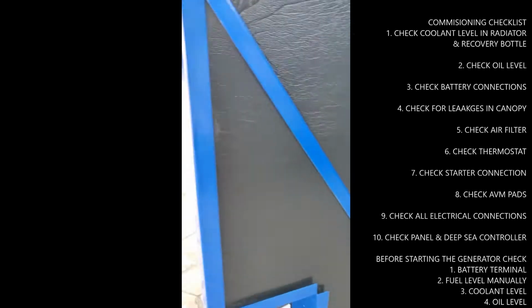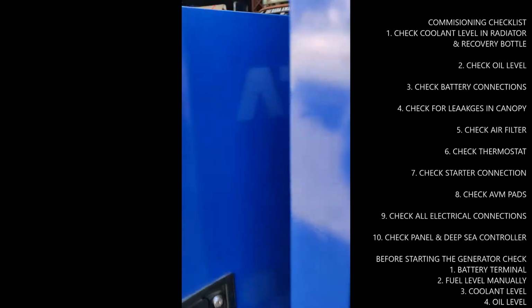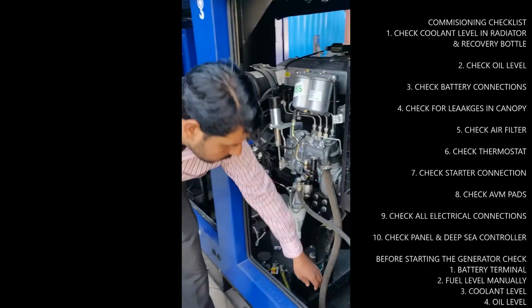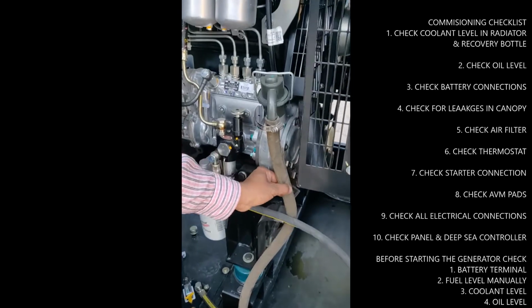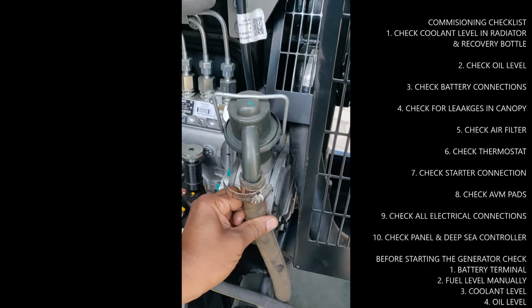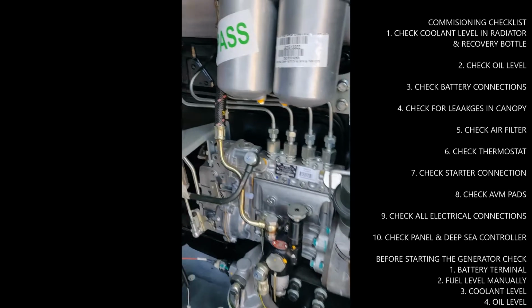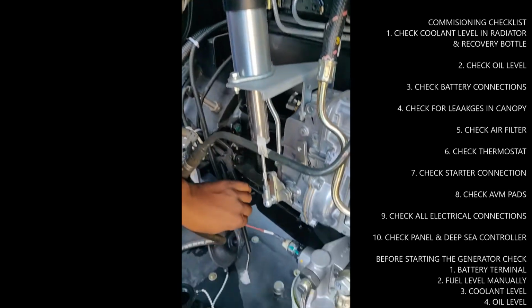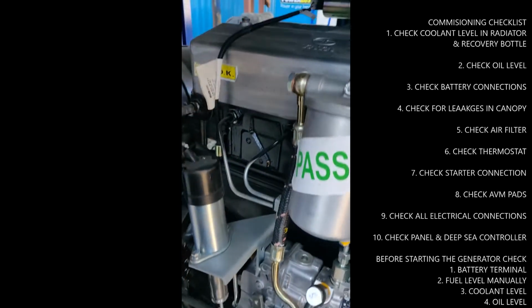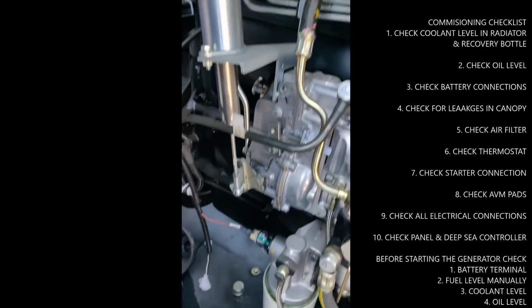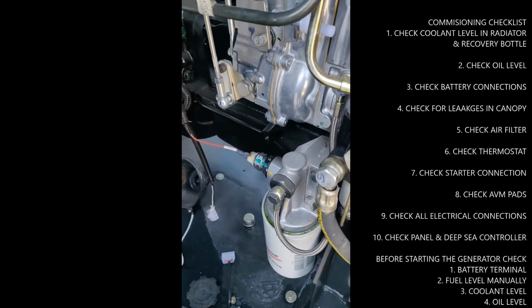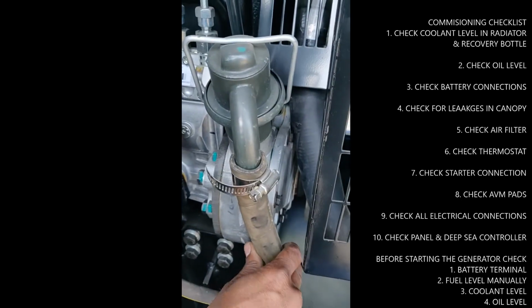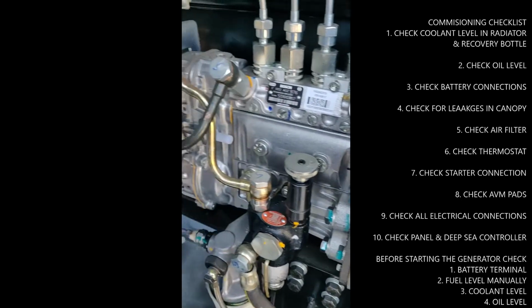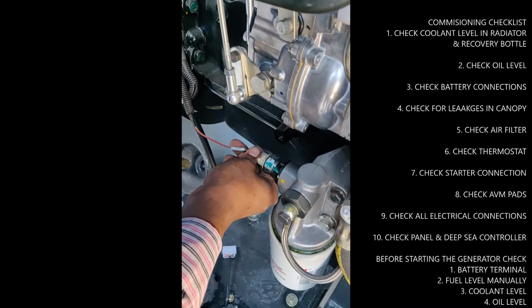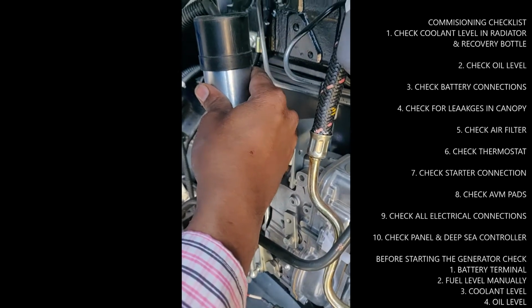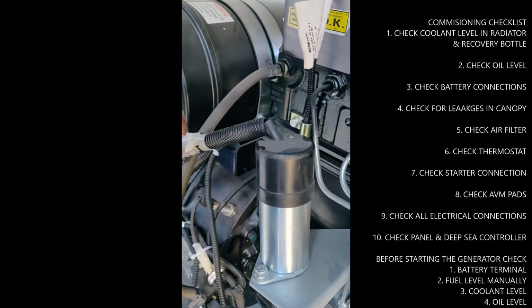Check the breather pipe that comes from outside the engine. This is the breather pipe. As you can see, it should be properly connected and fitted. Check the clamping of the pipe. Check that the solenoid coil and the connection are proper. Solenoid coil should be properly fitted and the connection should be proper. This is the oil sensor. Oil sensor should be properly fitted. Again, the breather pipe and the oil sensor. This sensor is very important as the safeties are attached to it. This is the starter solenoid.